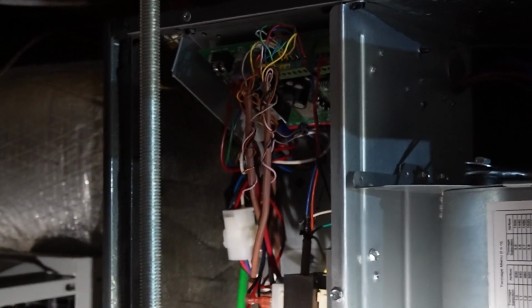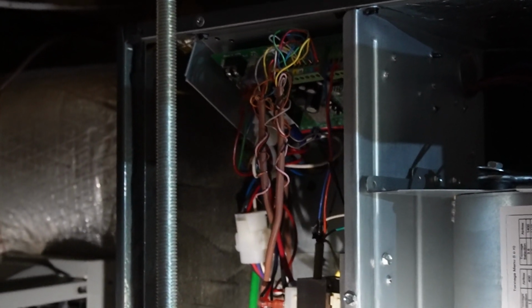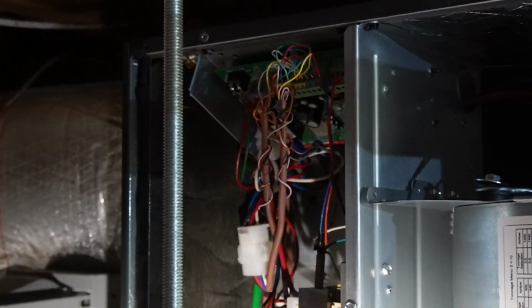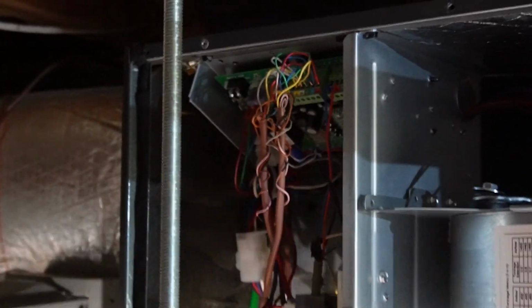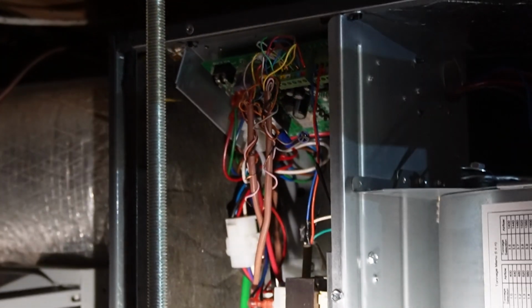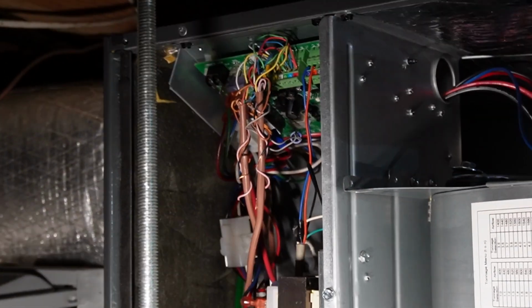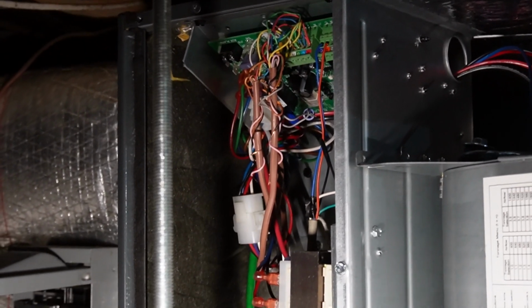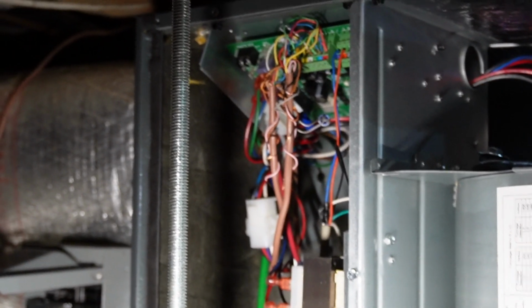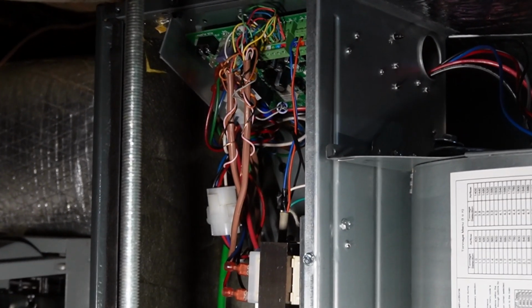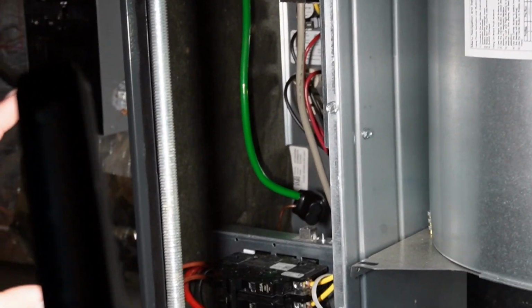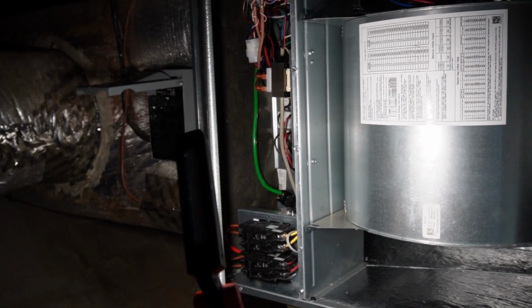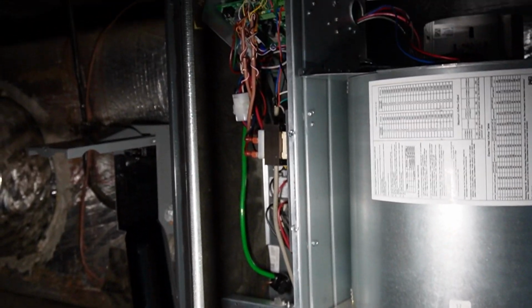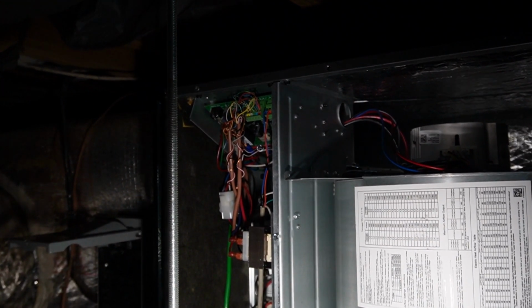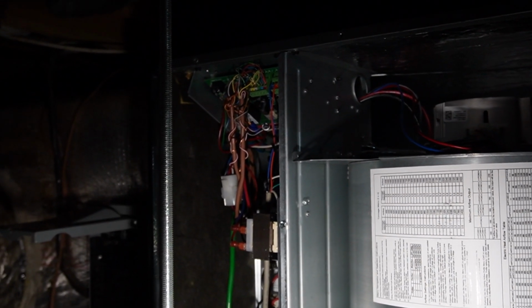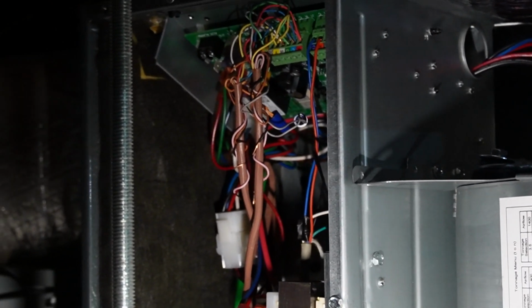So first, the white wire for auxiliary heat is in the W terminal. So in cooling mode, that runs the heat strips all the time on the Honeywell T-Series thermostats. Secondly, it's got 15 kW worth of heat on a 50 amp double pole breaker. So anytime those heat strips run, it's going to trip the breaker. Well, that'll do it. Auxiliary heat wouldn't have been running in heating mode because it was in the wrong terminal to be energized.